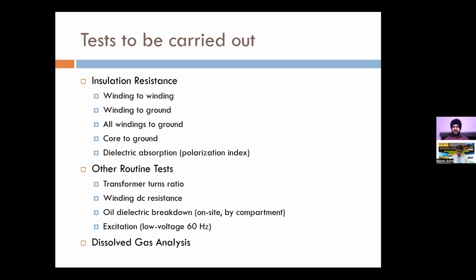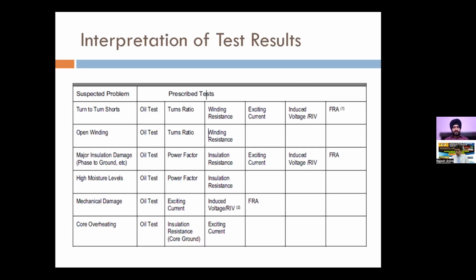Another test is the SFRA test, sweep frequency response analysis, which we mostly do, like I said, when we suspect a mechanical damage inside our transformer. It is also very helpful in indicating many minor disturbances inside our winding or bushing lead area. So this is a small interpretation of the test results.